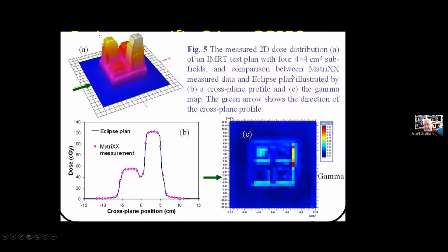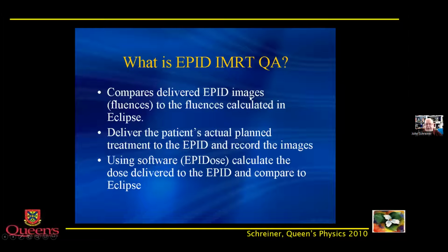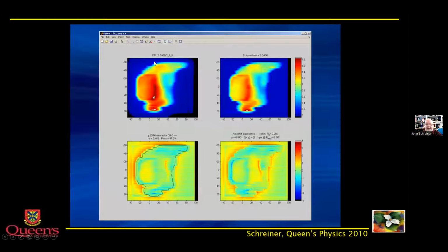And in Kingston, what they will do is they will actually use part of the linear accelerator design, which has a portal imaging device. So it has an imaging panel that is at the exterior of the patient on the other side of where the radiation beam is coming from. So I have the radiation beam coming, the patient is here, and I have this imaging device that I can look at to see that the intensity modulation that was planned by the treatment planning system has actually been delivered to the unit. And we do this before the patient goes on.